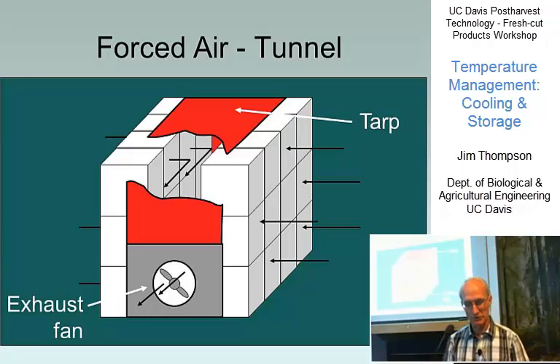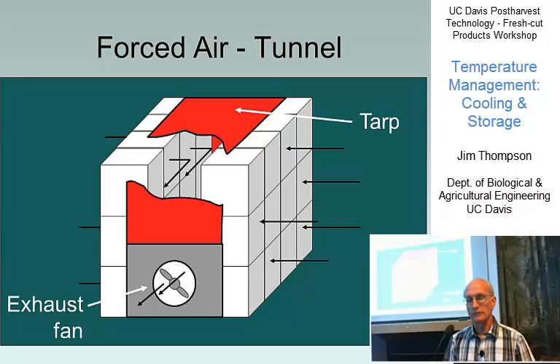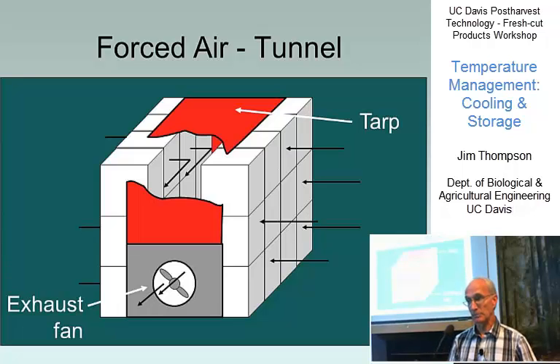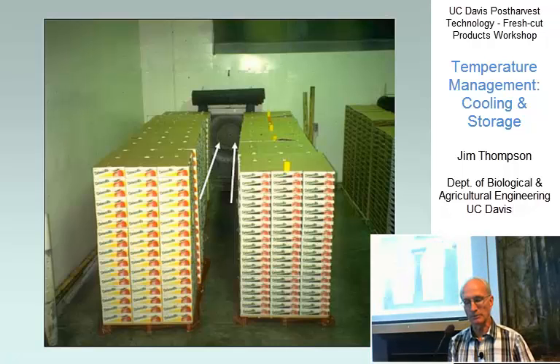That's what forced air cooling is about. You can see here there are two lanes of product in what looks like pallet bins. There's an empty space between them, and a fan evacuates air from that empty space. The tarp in red covers the empty space, so the air that's evacuated has to be replaced by air that flows through the product. It's a simple concept.